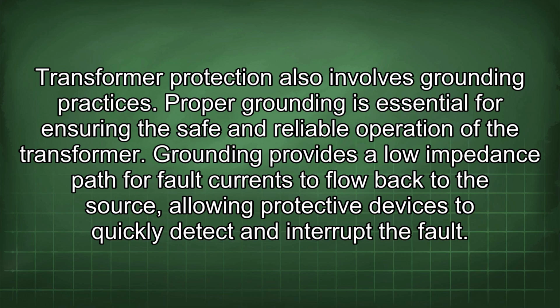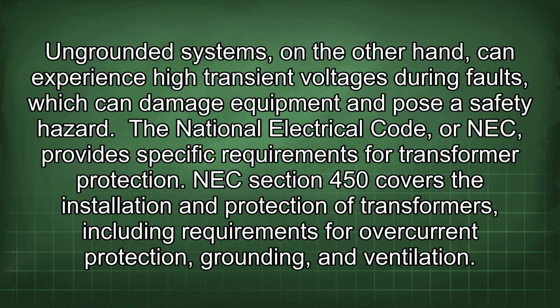Transformer protection also involves grounding practices. Proper grounding is essential for ensuring the safe and reliable operation of the transformer. Grounding provides a low impedance path for fault currents to flow back to the source, allowing protective devices to quickly detect and interrupt the fault. Ungrounded systems, on the other hand, can experience high transient voltages during faults, which can damage equipment and pose a safety hazard.